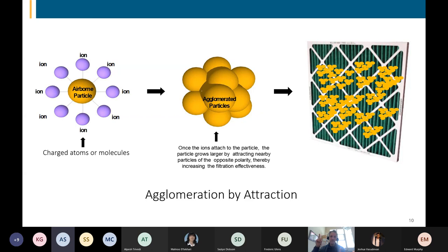We're not doing that on filters. We probably should be. Everybody assumes you put a HEPA filter into an HVAC system and it's going to get rid of 99.97% of the 0.3 micron size particles and more, larger and smaller. Not unless the particle gets to it. That's the difference between efficiency and efficacy that needs to be measured in the space environment itself. I highly recommend you do that.